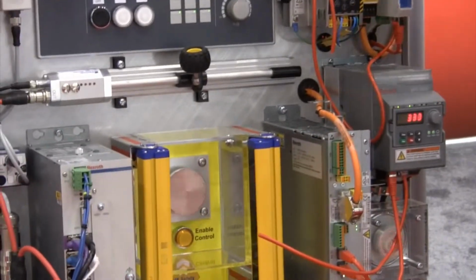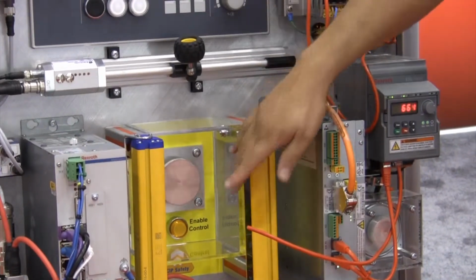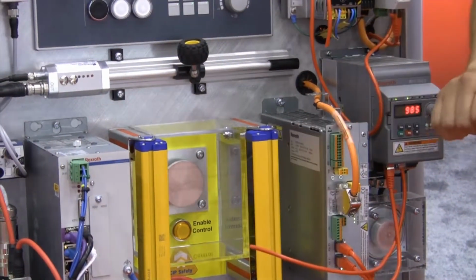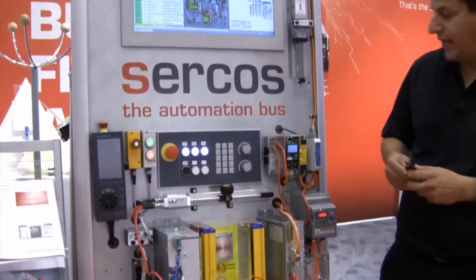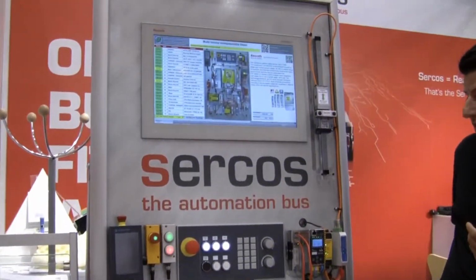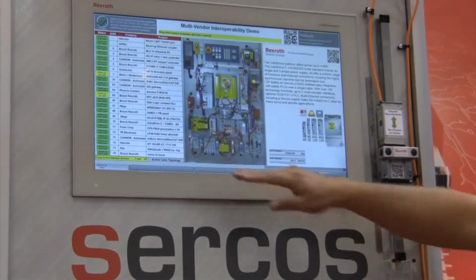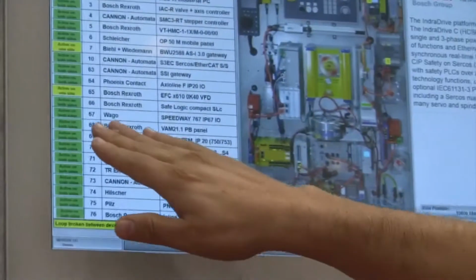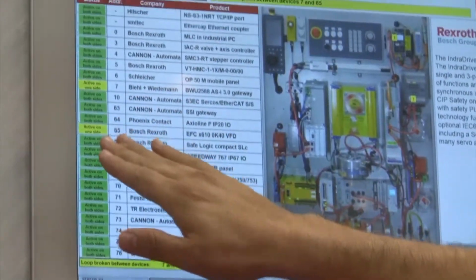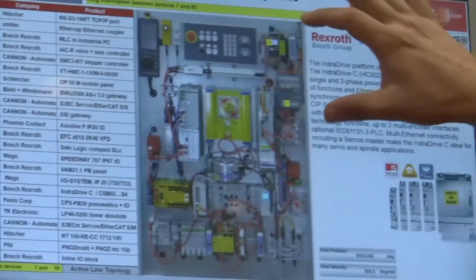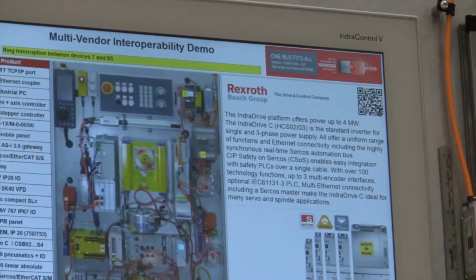You could see that everything on your machine still runs. The drive is still running, and the control will tell you where you have the break. So here, it's telling me that I have the break between address 7 and address 65. It's showing both of them here as broken.